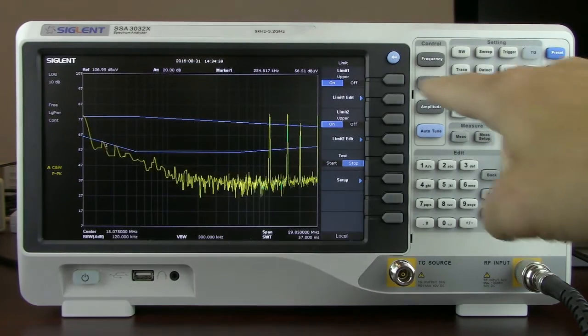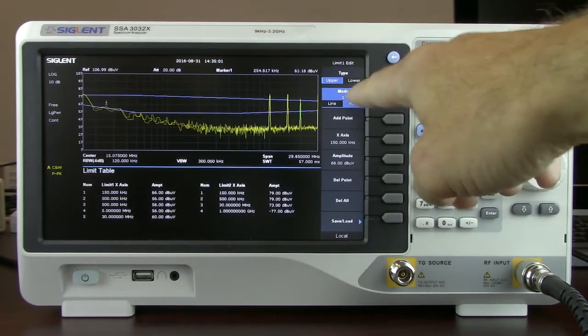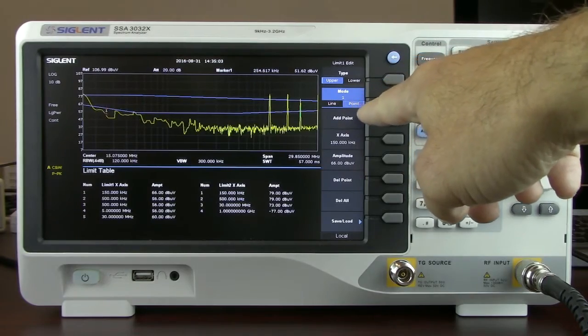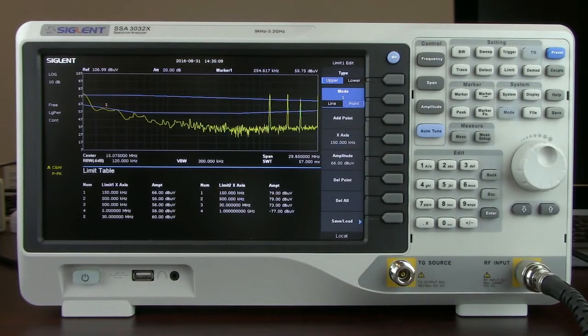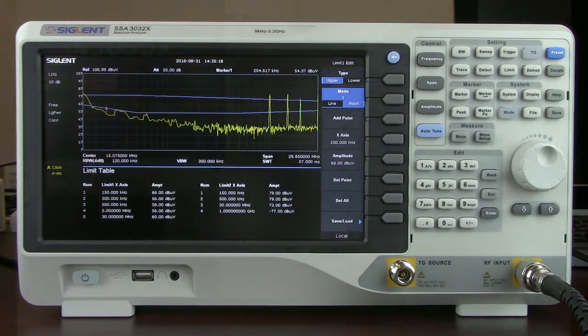Both of the limits can also be edited. They've got a line mode as well as a point mode. In the point mode you can see we've got the X axis as well as the amplitude values for each of the points in that particular test. All of these features are very helpful when performing pre-compliance. And there's also a software application that can help to sequence a lot of the data collection.